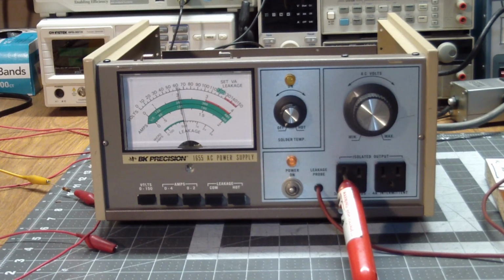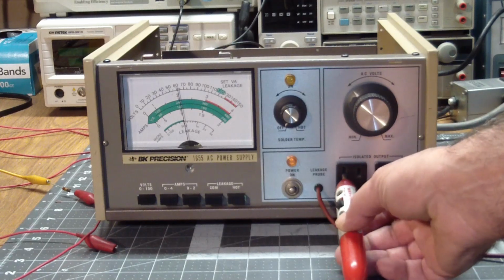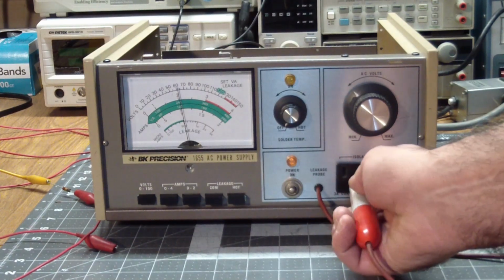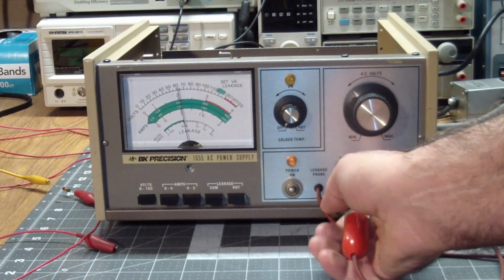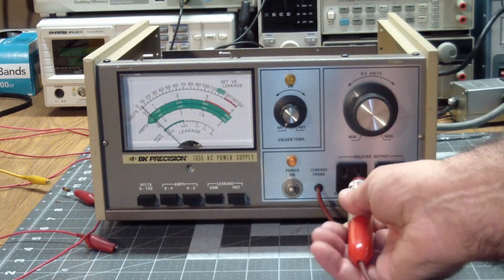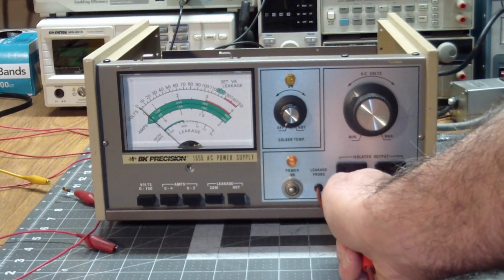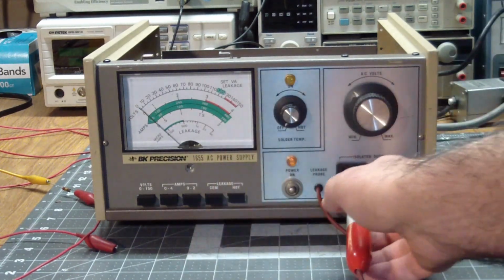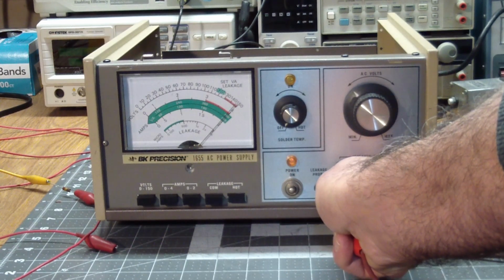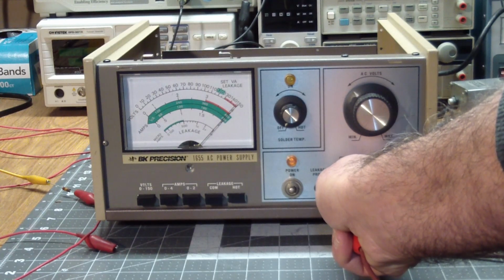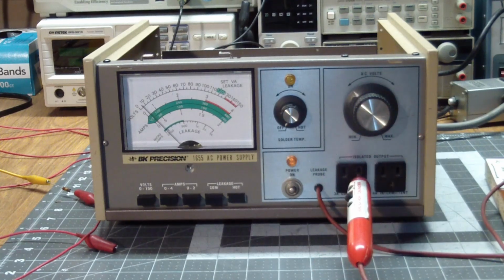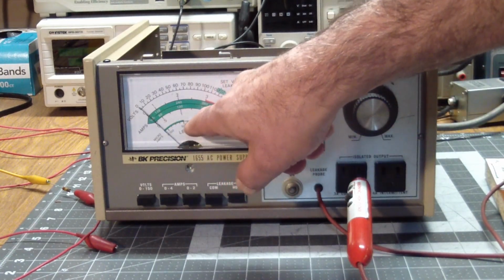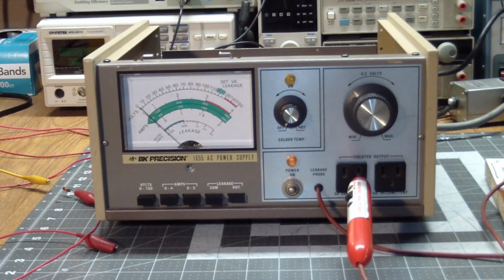And finally, you are supposed to check, this is basically in the hot leg, and if you go to the neutral leg, go back into leakage, it shouldn't show anything, and it doesn't. And then when you select hot on the leakage control, it goes back to the 5 milliamps. All right, so the leakage meter works, and I guess they don't explain it, but since from 0 to 500 microamps it's in the green range, that means you're okay. But once you're outside of that range, the leakage current is too high, and you get something really bad happening in your circuit.